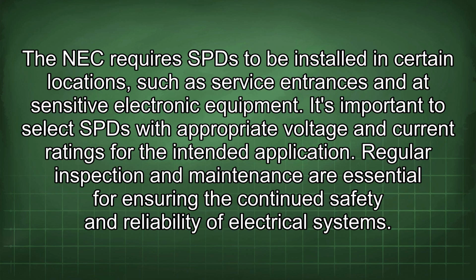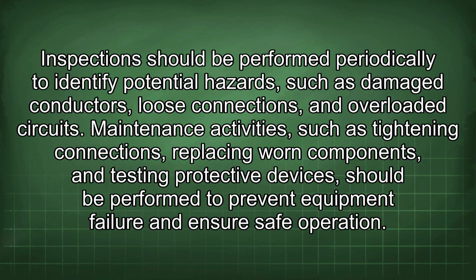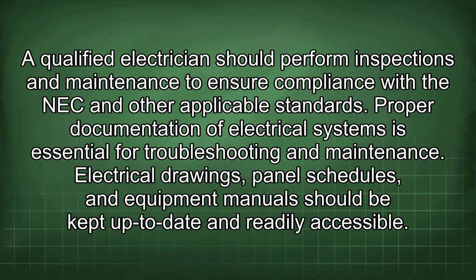Regular inspection and maintenance are essential for ensuring the continued safety and reliability of electrical systems. Inspections should be performed periodically to identify potential hazards, such as damaged conductors, loose connections, and overloaded circuits. Maintenance activities such as tightening connections, replacing worn components, and testing protective devices should be performed to prevent equipment failure and ensure safe operation. A qualified electrician should perform inspections and maintenance to ensure compliance with the NEC and other applicable standards. Proper documentation of electrical systems is essential for troubleshooting and maintenance.